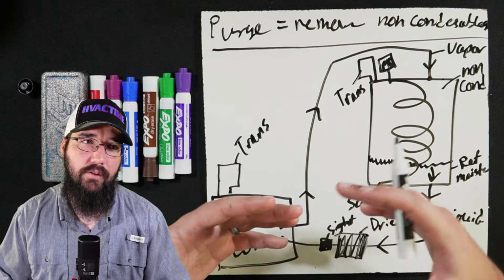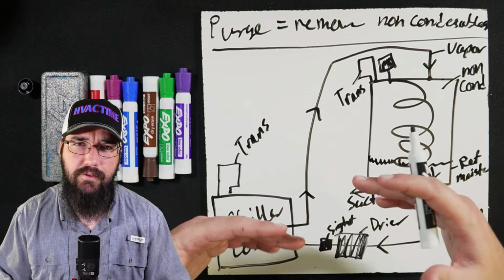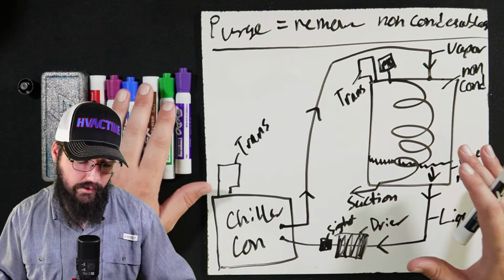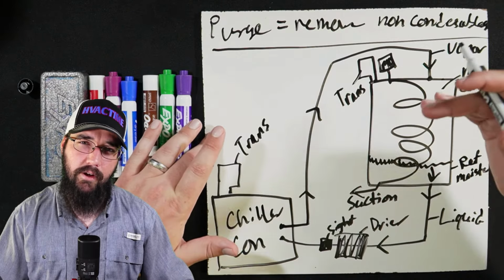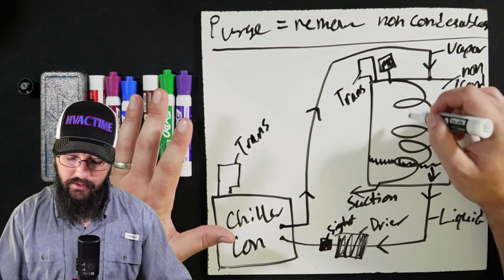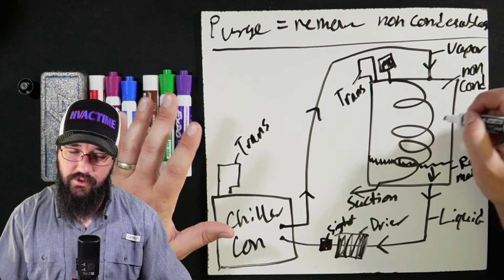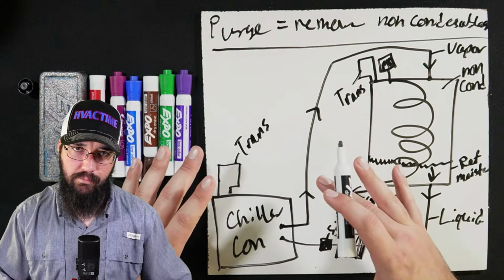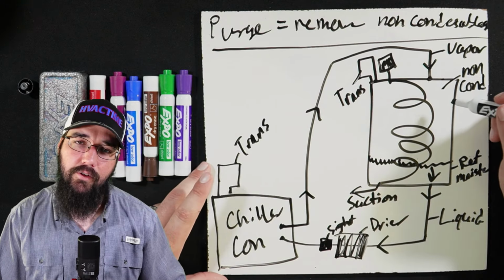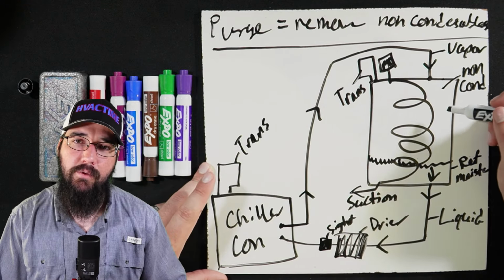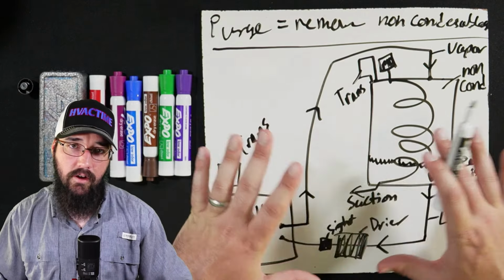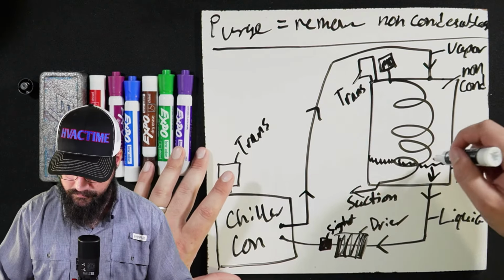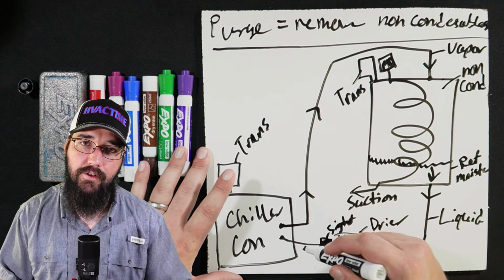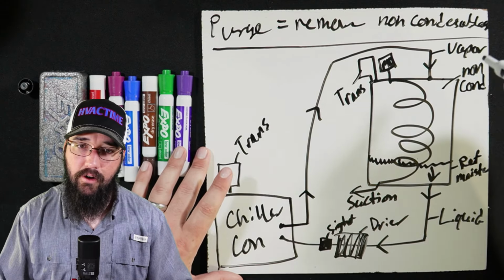Now, I think it's somewhere like 2 to 3 psi or 2 to 3 degrees of saturation. I forget exactly which it is. I'd have to verify that in the book. But once we cross that threshold, where this gets slightly higher than the chiller's condenser barrel pressure, that is how York is determining, okay, now it's time to initiate a pump out cycle. So at that point, the purge unit and system still keeps running. That never shuts off just because we go into a pump out, and we don't isolate any valves coming to the chiller.